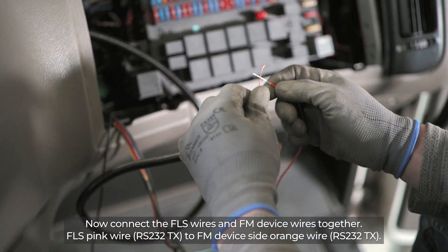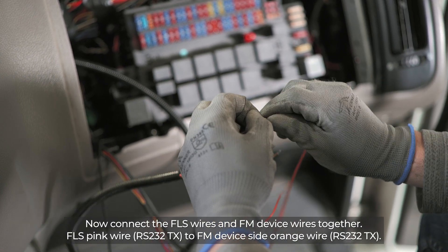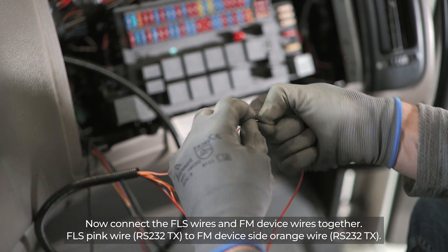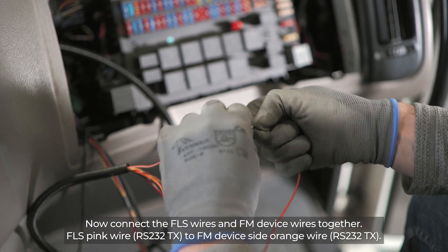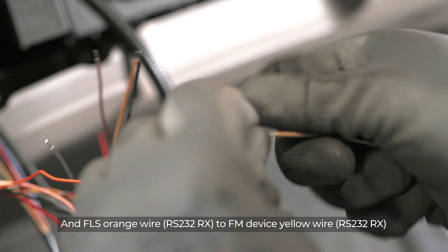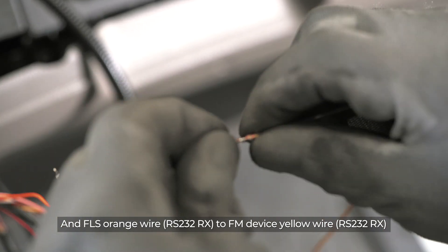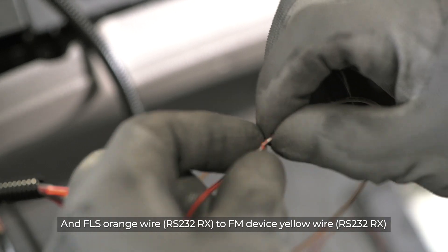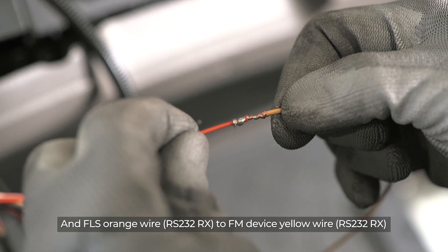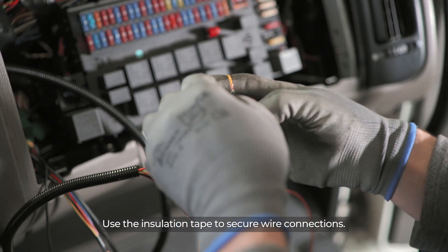Now connect the FLS wires and FM wires together. FLS pink wire RS-232-TX to FM device side orange wire RS-232-TX. Use insulation tape to secure the wire connections.